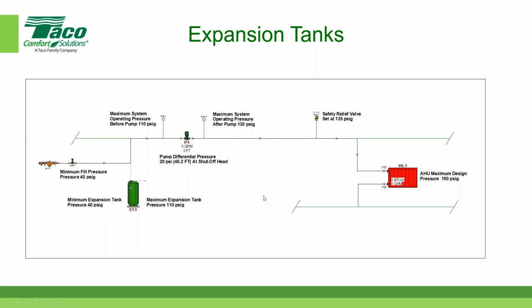So here's what happens. If the tank is too physically small, then in our example right here, as the temperature of the system goes from 50 degrees to 180 degrees, the water would expand. There'd be less place for the water to expand into, and so it would reach the maximum pressure halfway through. I'm just going to say halfway through. It would reach the maximum pressure that we designed the system for during the expansion process. So before it gets to the maximum temperature, it would exceed 110 pounds. If it exceeded 110 pounds by a few pounds, it would set off the safety relief valve.